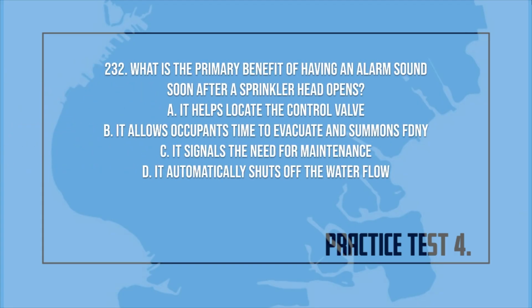232. What is the primary benefit of having an alarm sound soon after a sprinkler head opens? A. It helps locate the control valve. B. It allows occupants time to evacuate and summons the fire department. C. It signals the need for maintenance. D. It automatically shuts off the water flow.